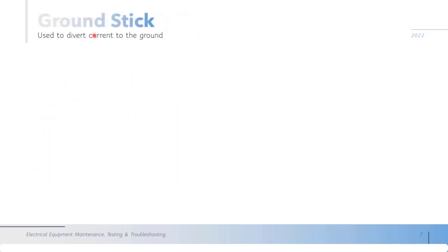And another basic tool is the ground stick, and it is used to divert current to the ground. As I said before, sometimes in medium voltage, even in high voltage, you can have residual voltage. This residual voltage can reach values like 1 kV or 2 kV. So if you touch this voltage you will get electrocuted. To avoid this electrocution we use the ground stick. Also sometimes in motors you will find charged capacitors, so it's better to ground the terminals of the motor, so when you touch it the current will not pass through your body but will divert to the ground because you connected the ground stick to the circuit.